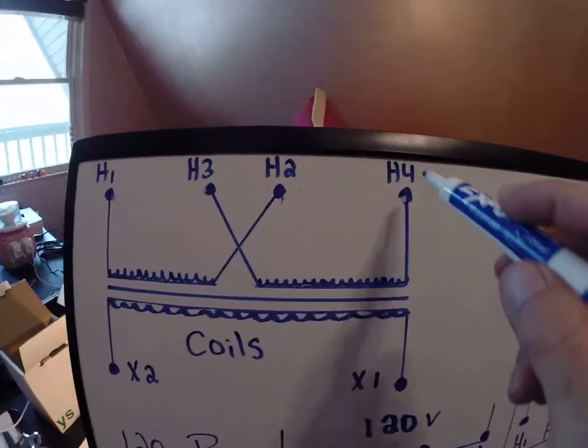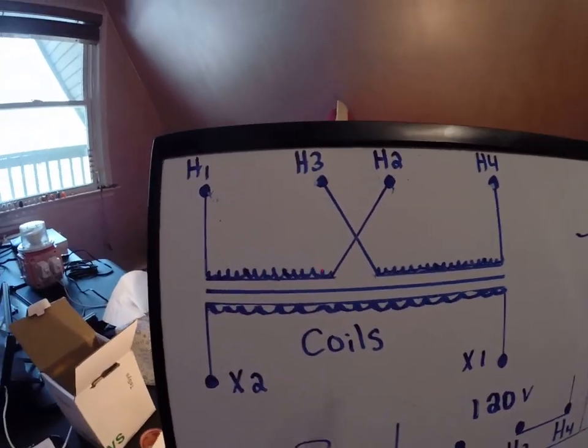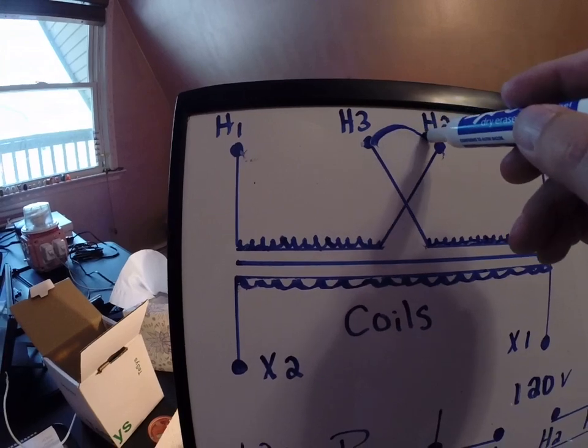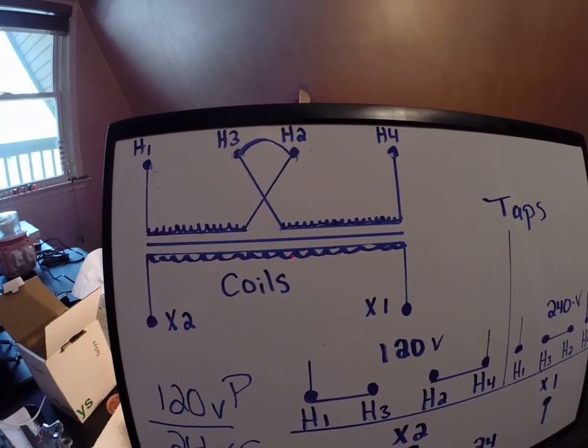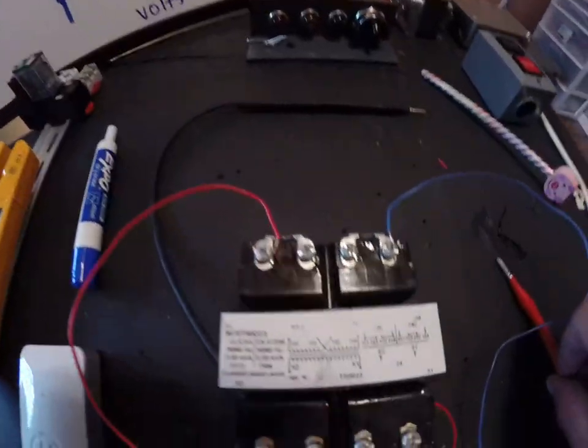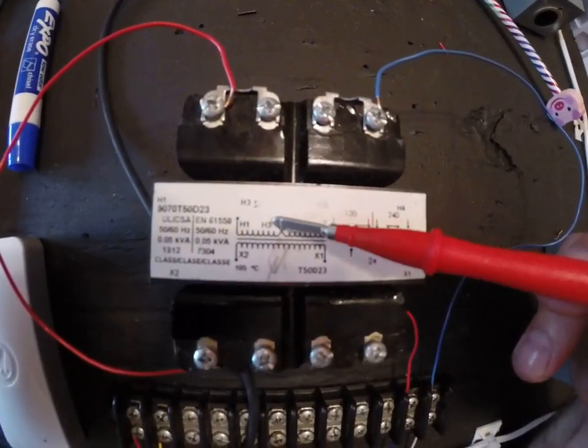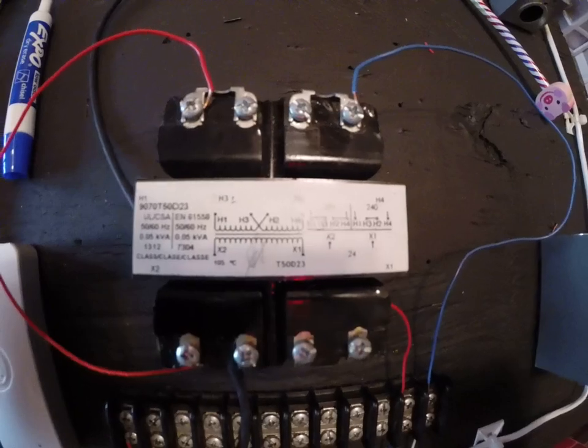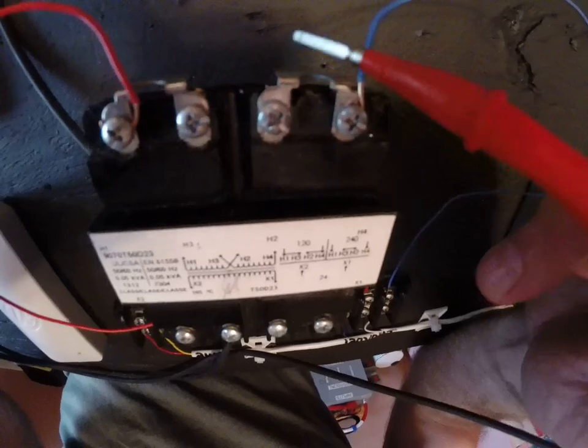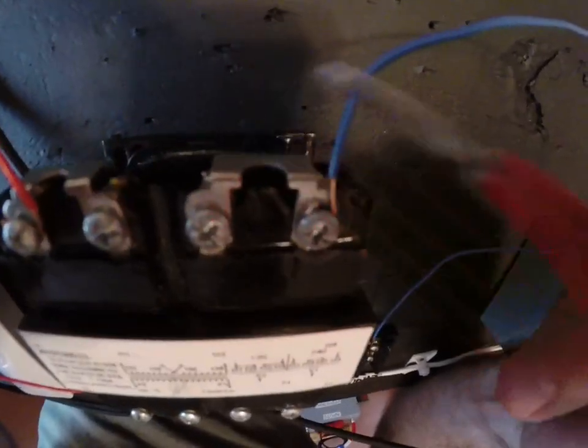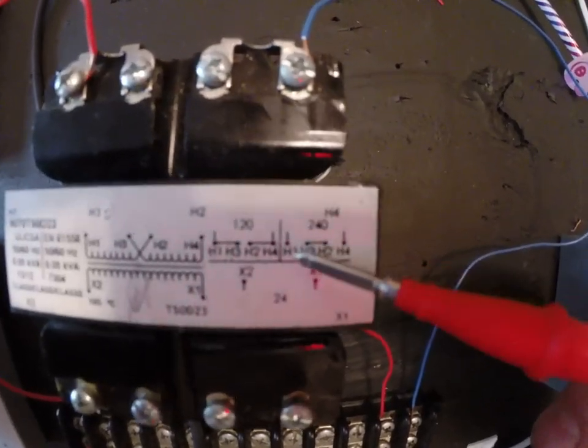So here's one winding from one screw to the other. And here's another winding from one screw to the other. If we attempt to tap them in series, we'd be putting in a jumper like this. That's what that means. Now let me show you how that's shown on the schematic. When we come back down here, if we look, I just put a jumper between these two items. And that represents this jumper. These come with these little factory jumpers right here. There's two of them on here.